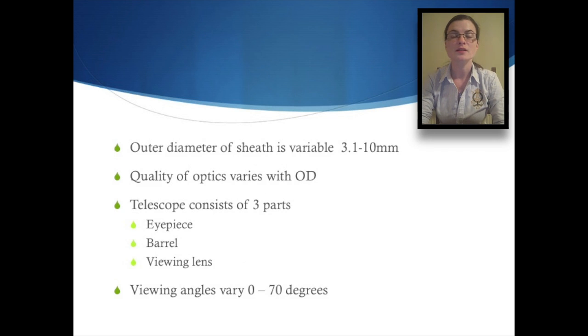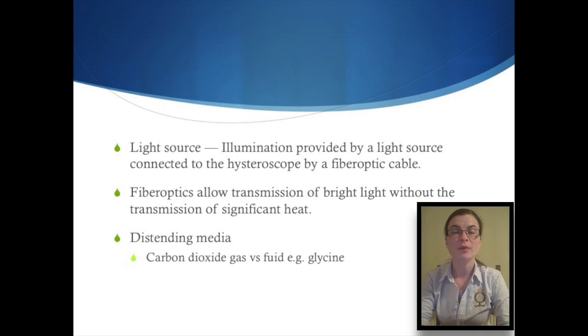It consists of an outer sheath or metal tube which surrounds channels for the telescope, distending media inflow and outflow, and operative instruments. Illumination is provided by a light source which is connected to the hysteroscope by a fibre optic cable.